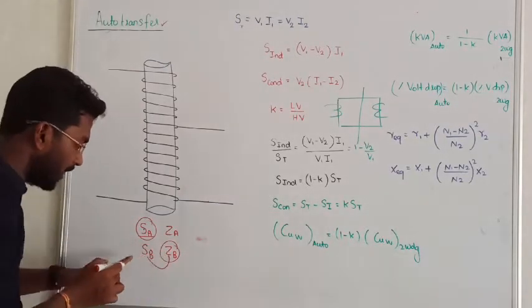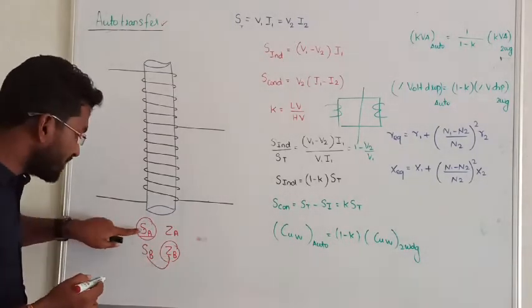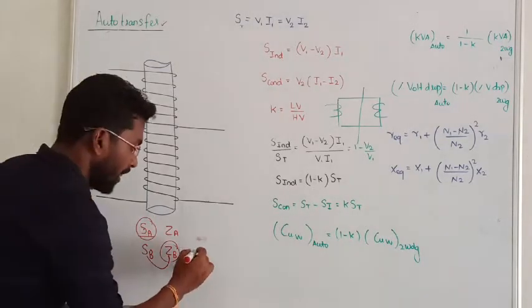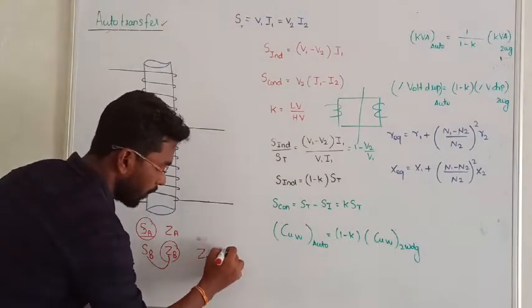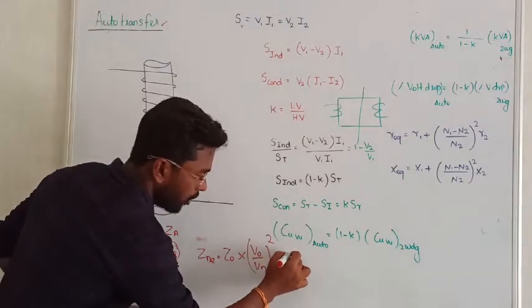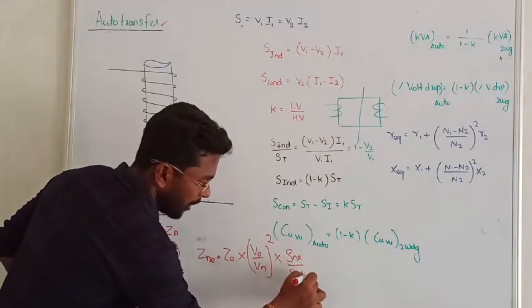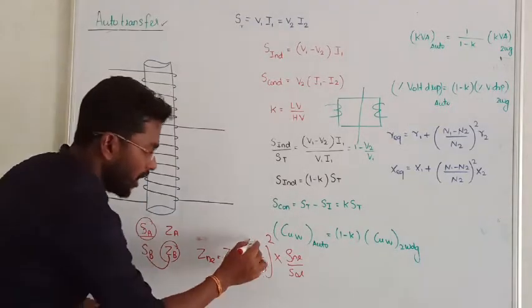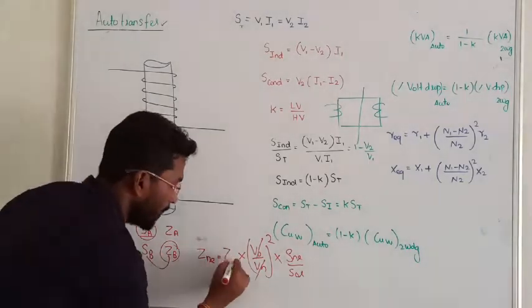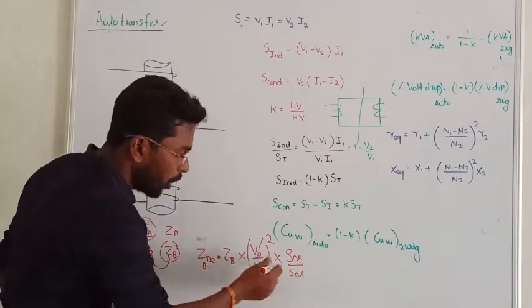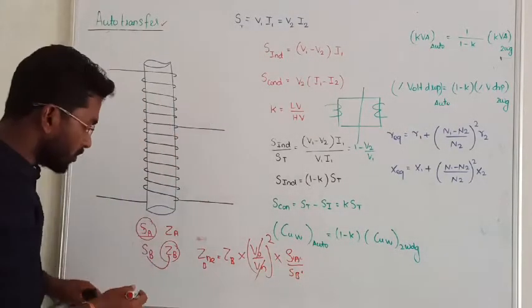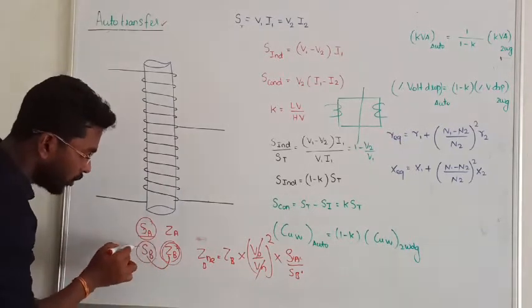ZB is the apparent power corresponding impedance for a given base SA. The new impedance value will be: old impedance multiplied by (old voltage divided by new voltage) squared, multiplied by (new apparent power divided by old apparent power). In parallel operation, voltage remains the same so those terms cancel, giving ZB_new = ZB_old multiplied by (SB_new divided by SB_old).